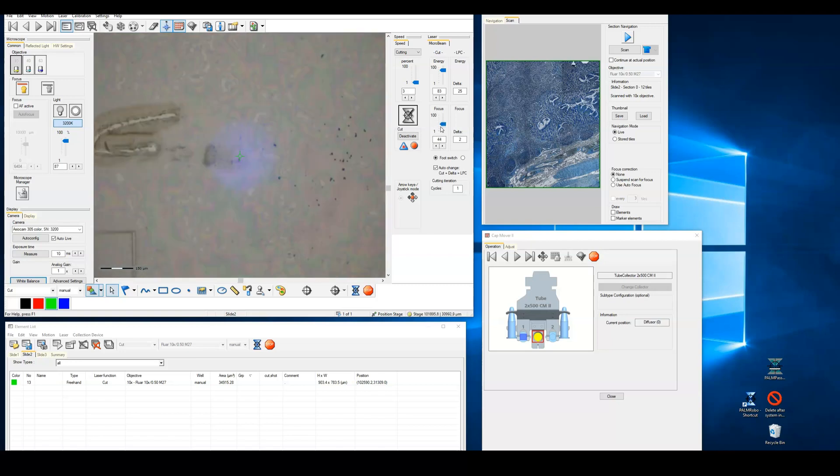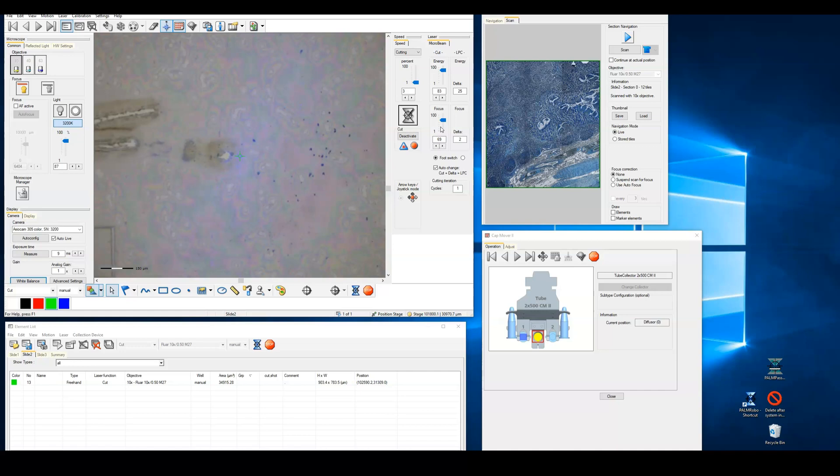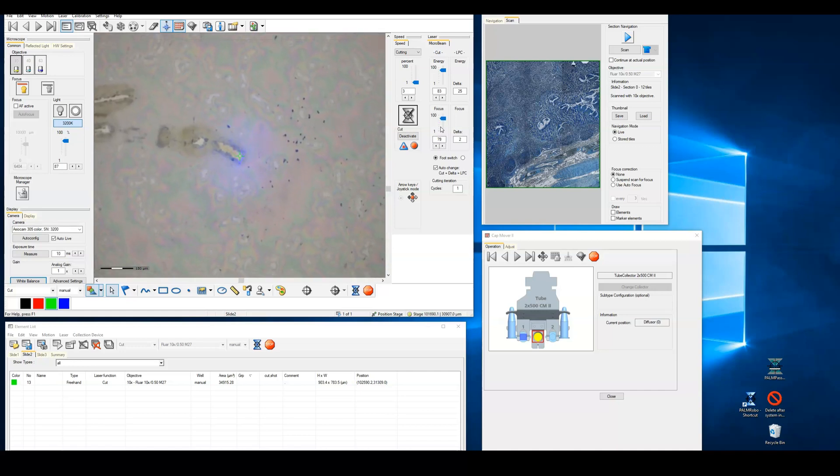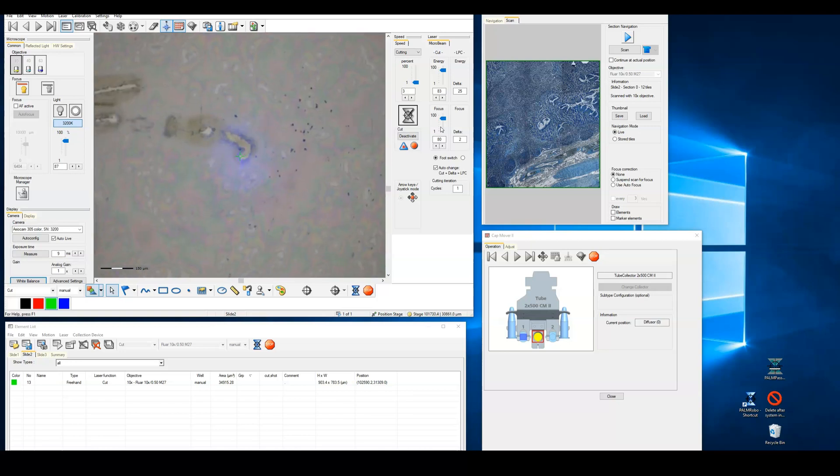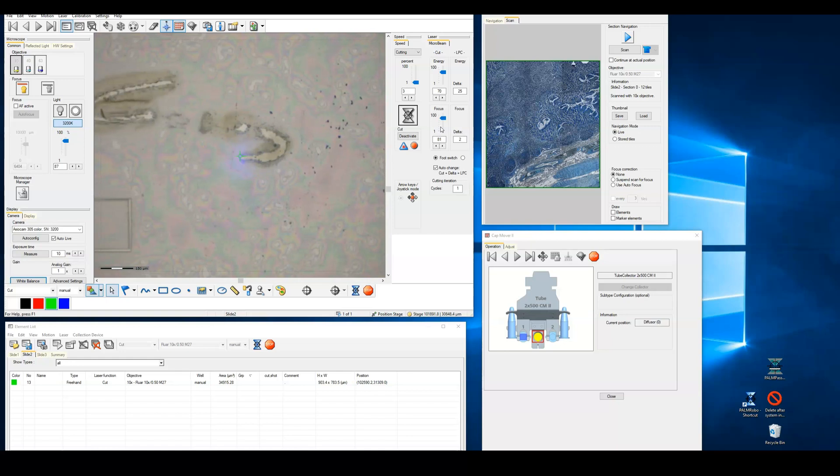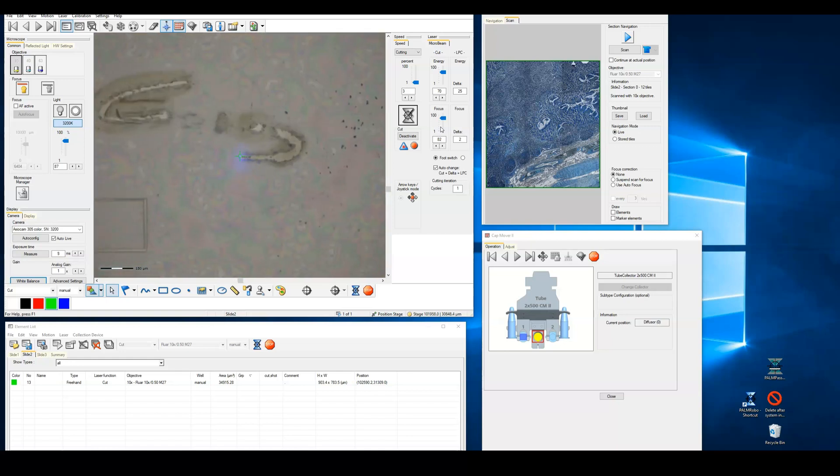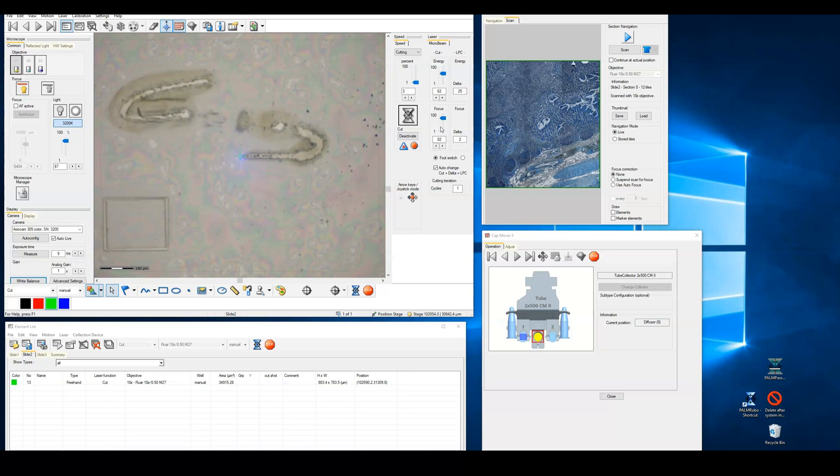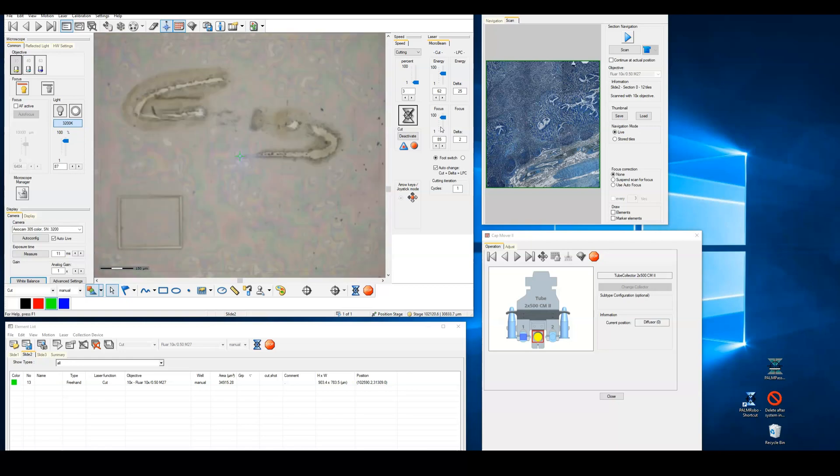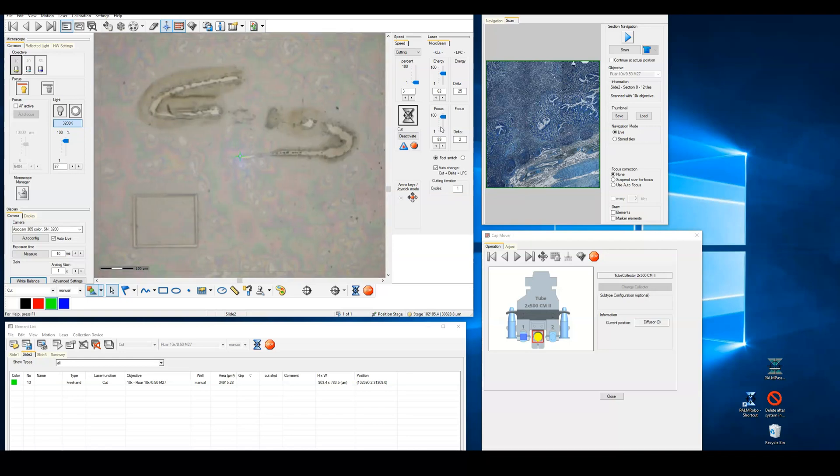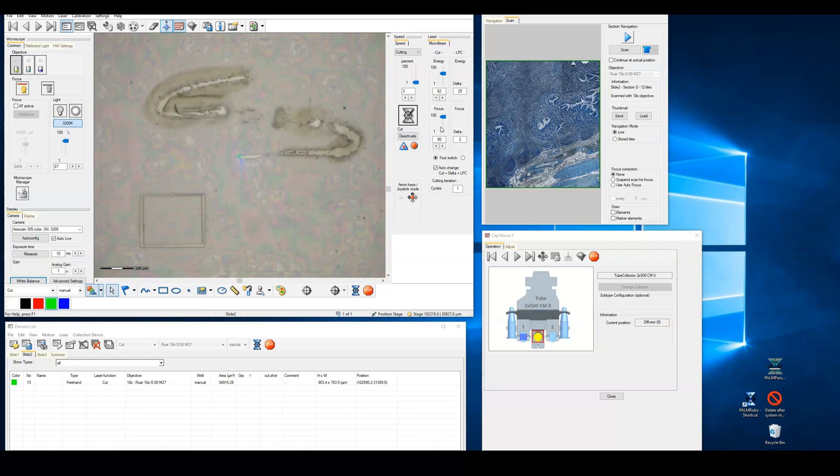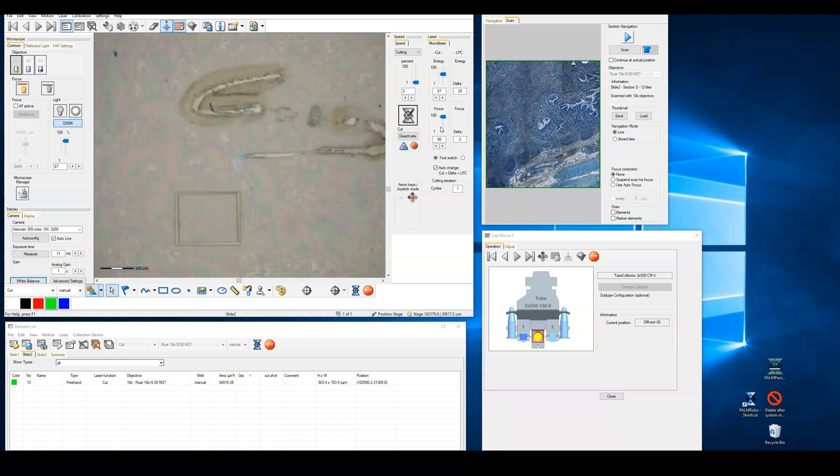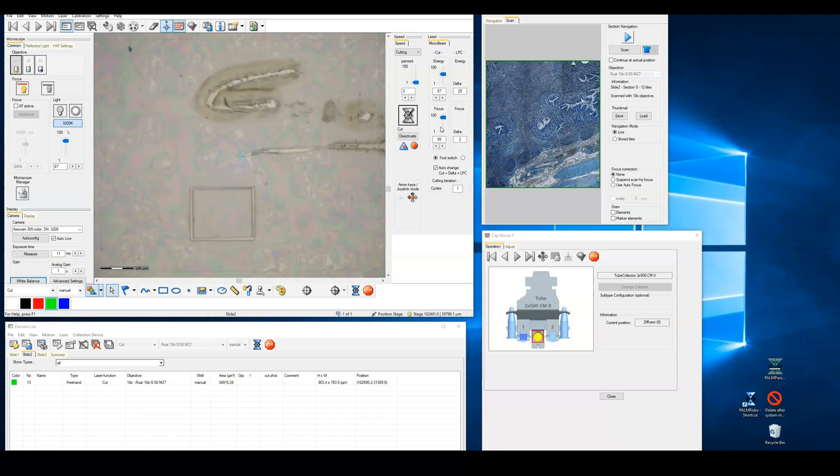Now that the laser is in a better focus position, reduce the laser power. Repeat this process for focusing and adjusting the power until you have a narrow cut line, and adjusting the focus either up or down reduces the effectiveness of the cut. This indicates that you've completed optimizing the cut laser. You may find that as you move to your tissue, it is necessary to increase the power slightly. Different tissues cut with different efficiencies, but having the cut optimized on the membrane should provide a starting point that's very close to the working conditions for your sample.